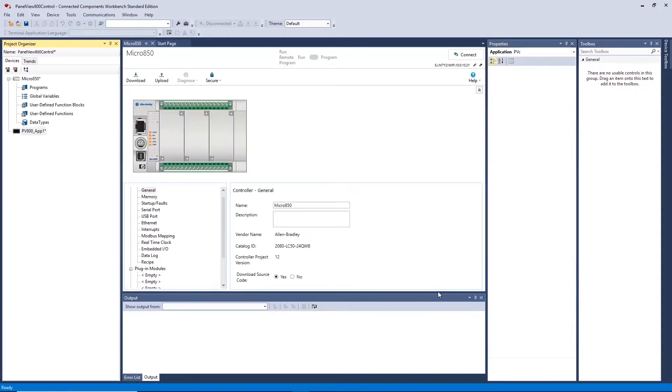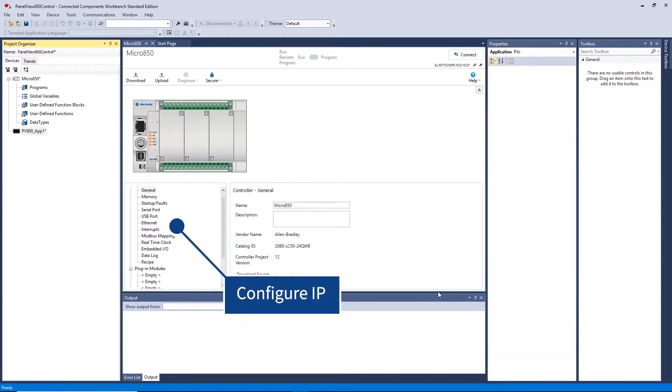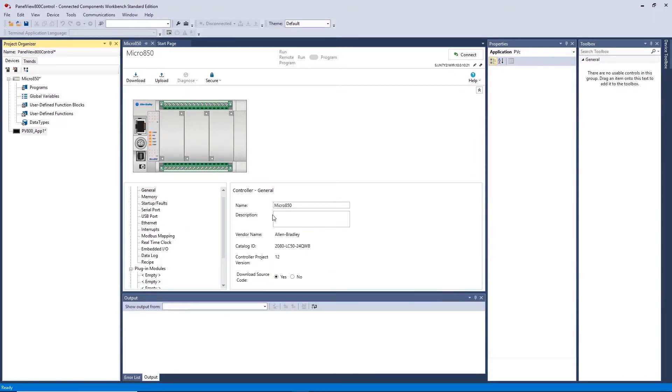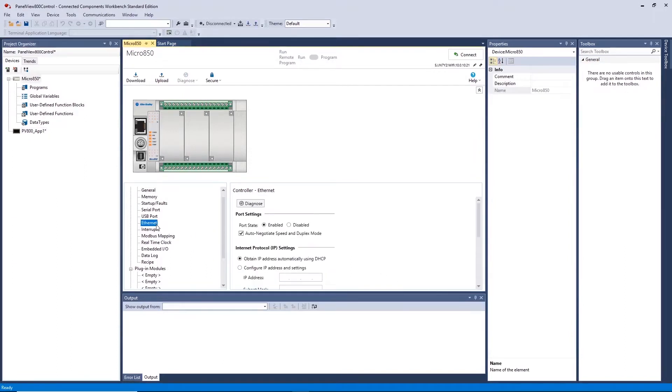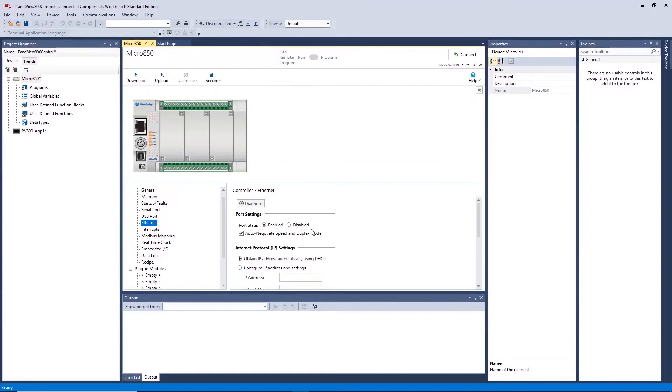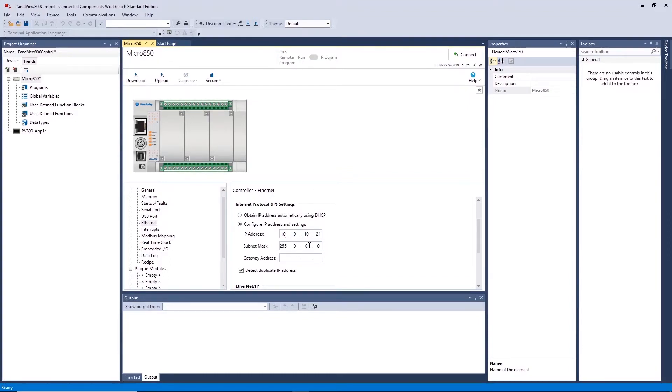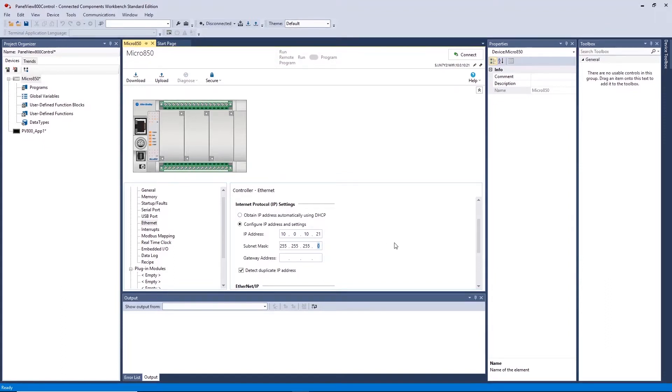First it is important to configure the IP address of the controller. This will change the addresses when the program is being downloaded to the controller. This can be different to the existing IP address that you have set for your controller over the network. However note that you will lose connection after download of the program if this IP differs from the subnet that your computer is on.